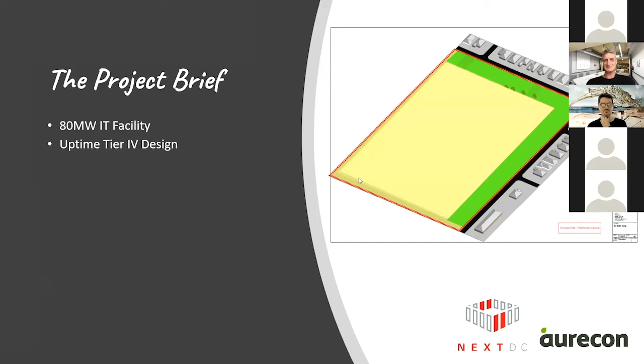Average rack power density of 4.5 to 13 kilowatts per rack — think of a bar heater, that's 6 or 7 bar heaters per rack. In a data hall with 400 racks, you're looking at 2 to 5.2 megawatts per 1,000 square meters of data hall.